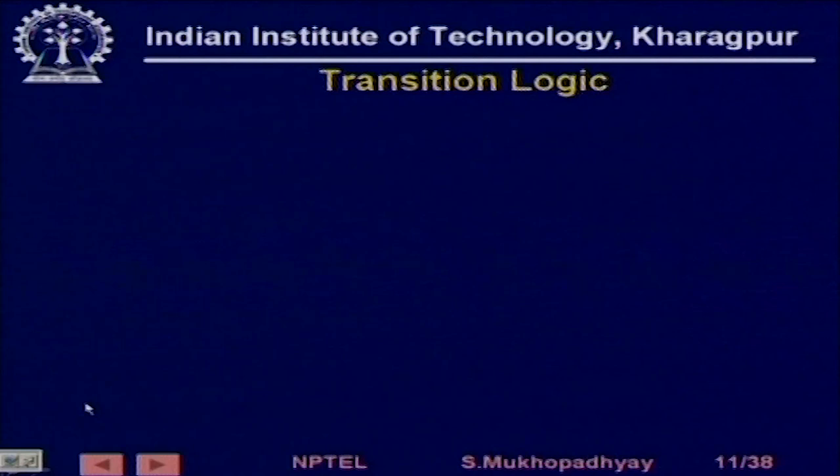Having done that, we can start developing our program. We have seen that as the system moves on, the various state logics and transition logics are alternately computed. First, there is a state in which some state logic will be satisfied. Depending on that, outputs will be exercised. After that, at some time, some transition logic will get satisfied. So now the system will come to a different state. The previous state logic is going to be falsified and the new state logic will now become true. Then, based on that, the corresponding outputs will get exercised. So this we have to now capture in a relay ladder logic program.